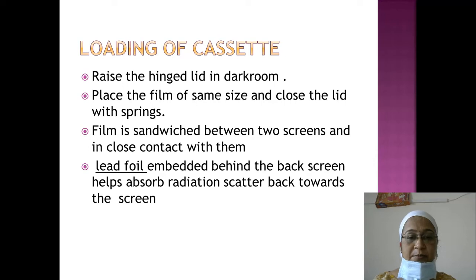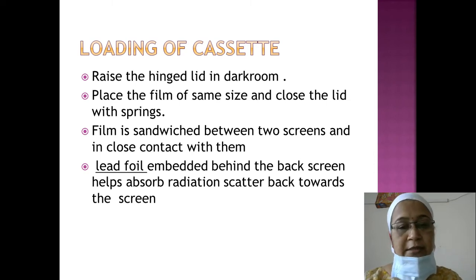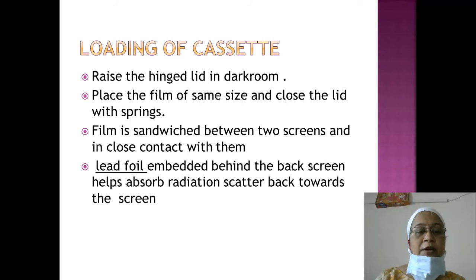The film should be the same size as the cassette. The film is sandwiched between two screens and must be in close contact with them. The cassette is then closed with metal springs. The lead foil embedded behind the back screen helps to absorb radiation scattered back towards the screen, preventing it from reaching the film and degrading image quality.